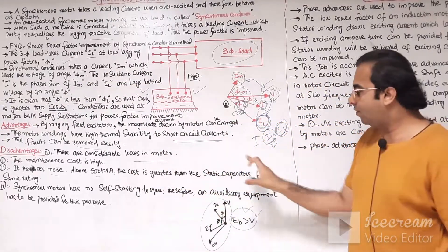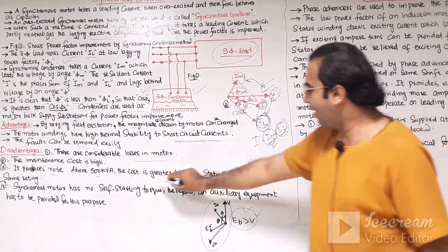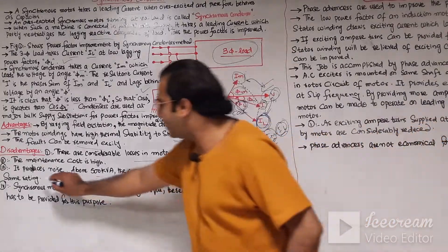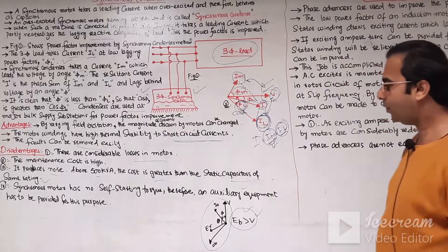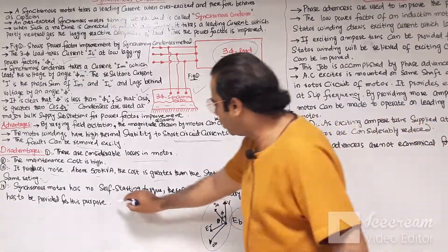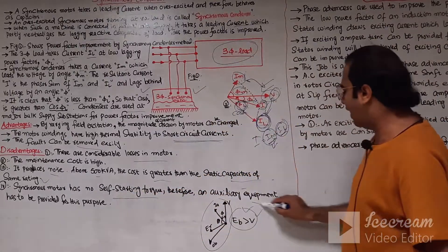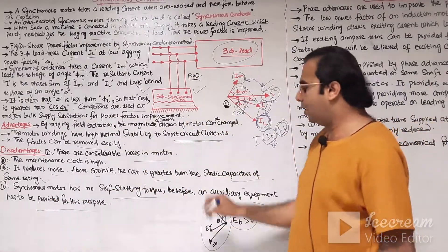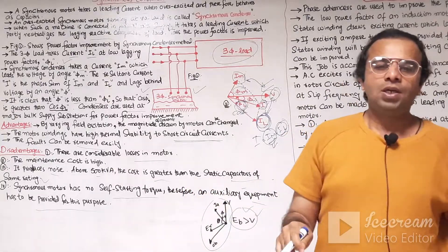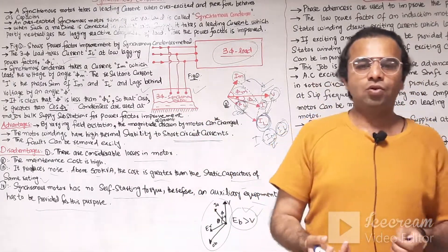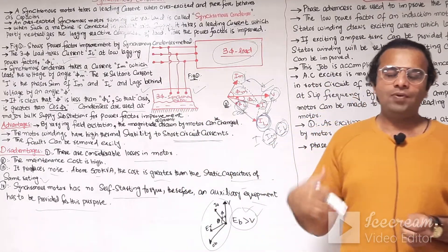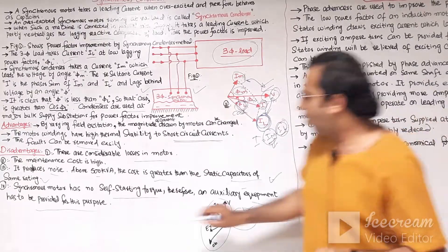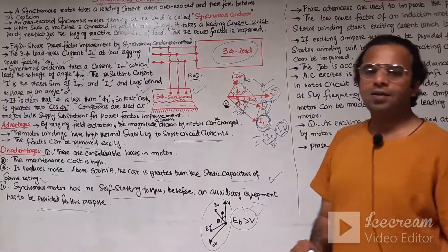Above 500 kVA, the cost of the synchronous condenser is greater than that of a static capacitor of the same rating. Additionally, the synchronous motor has no self-starting torque; therefore, auxiliary equipment must be provided for this purpose, since the rotor requires an external source to start rotating.